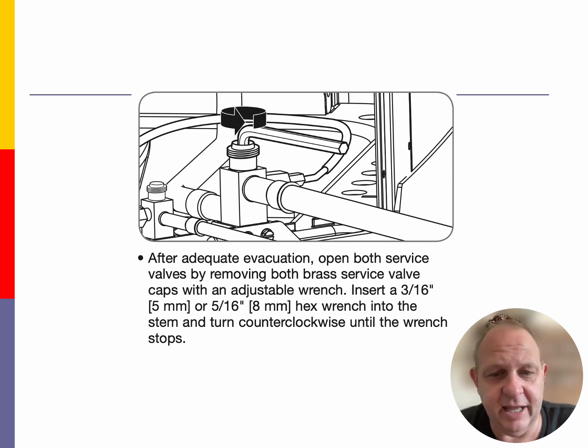We're going to use a 3/16 and a 5/16 hex wrench. They do make special tools out there that make this a lot faster. But anyway, this is what we're going to be doing, counterclockwise. Take it all the way to the end, and it's going to be fully open. And your Schrader valves should have been installed by this point. After you get done putting refrigerant in there, and like I said, there's different ways that we can do this, and we'll teach you about these when we get to it.